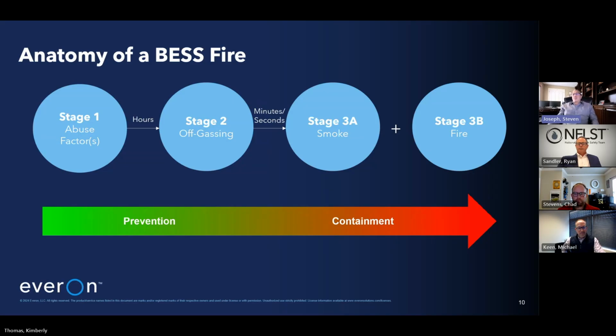But as the condition progresses, the fire potentially risks explosion from combustible gas formation. So again, in the absence of combustible gas detectors such as H2 to control ventilation as part of the deflagration system, we've got to be ensured that gas concentrations are below explosive limits in accordance with prescribed criteria.